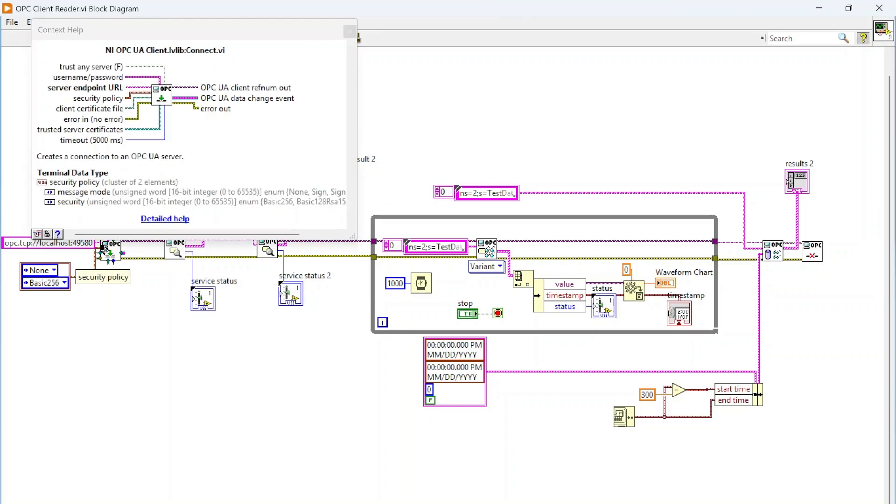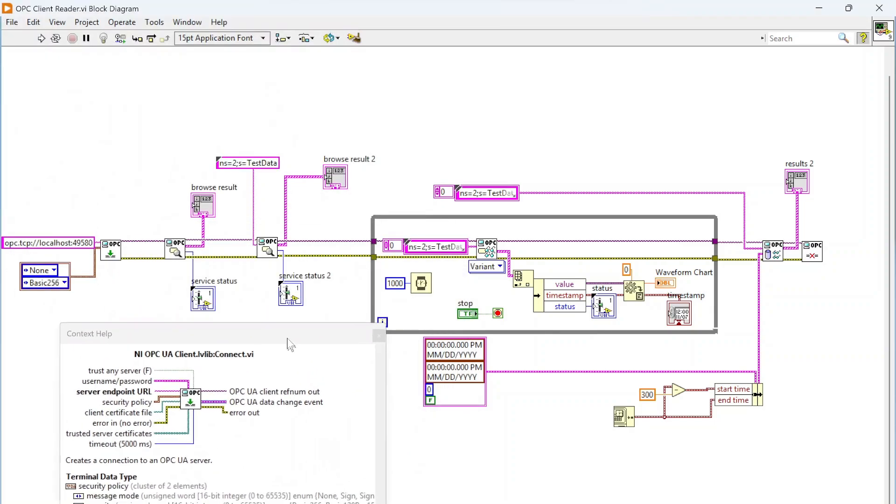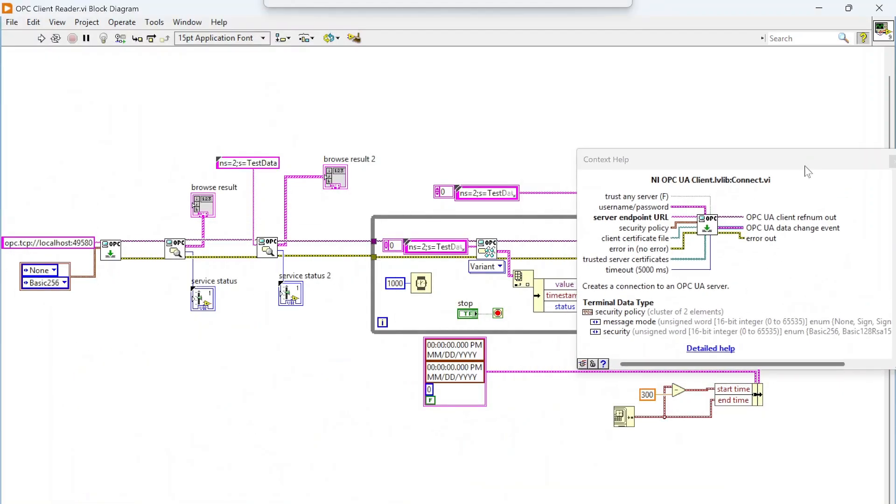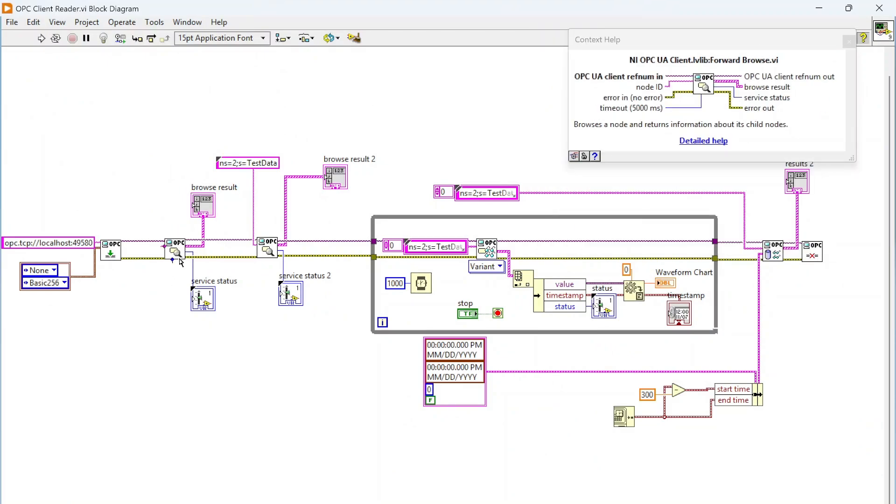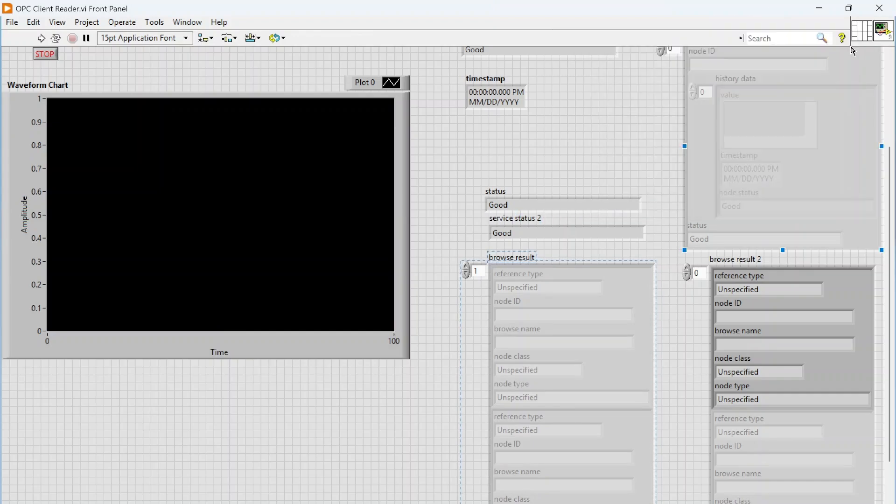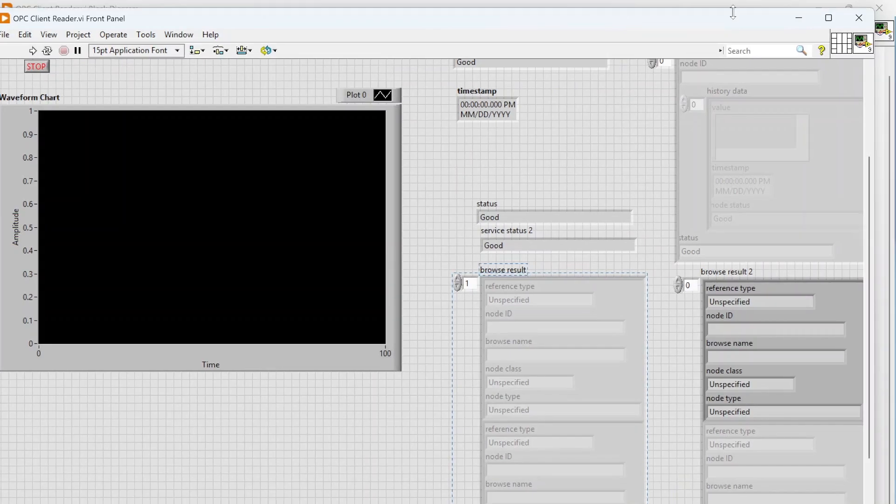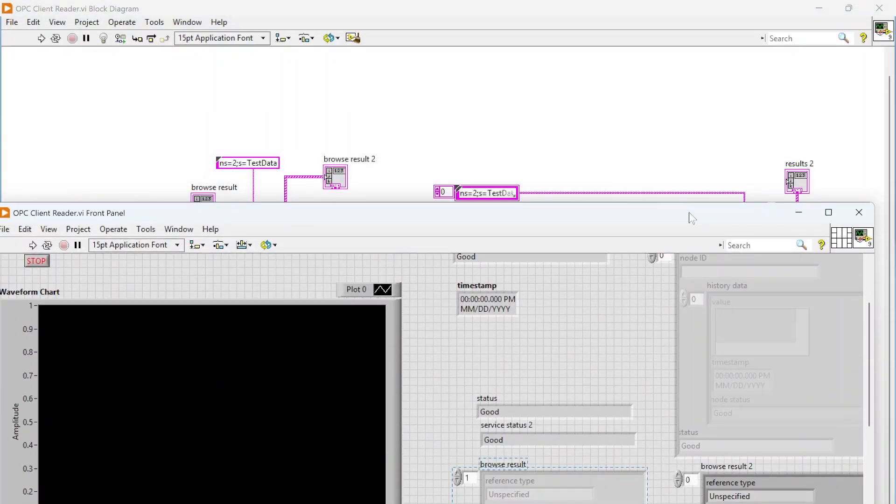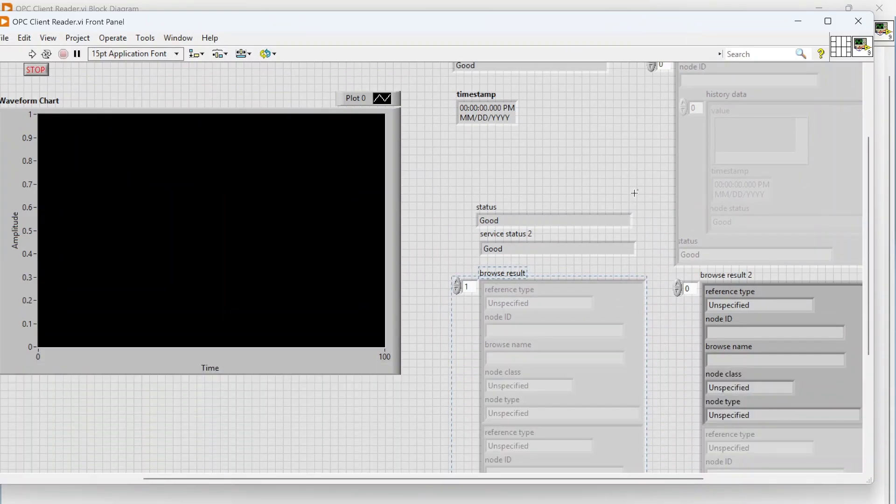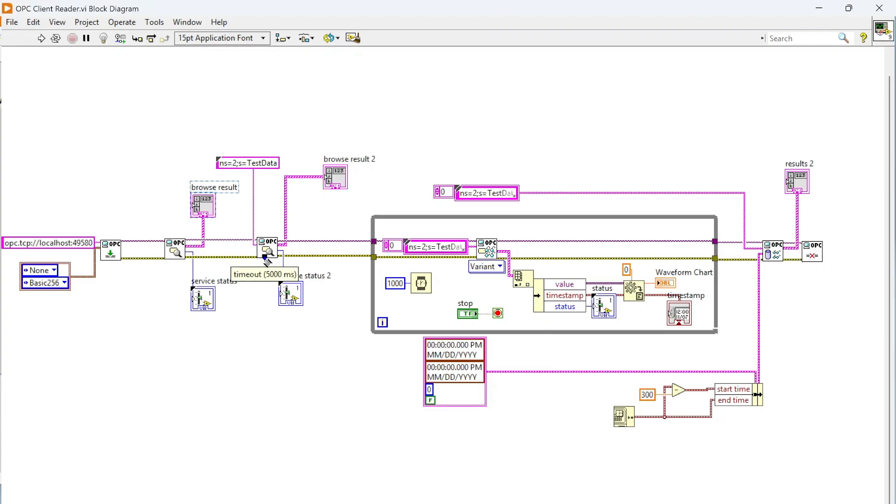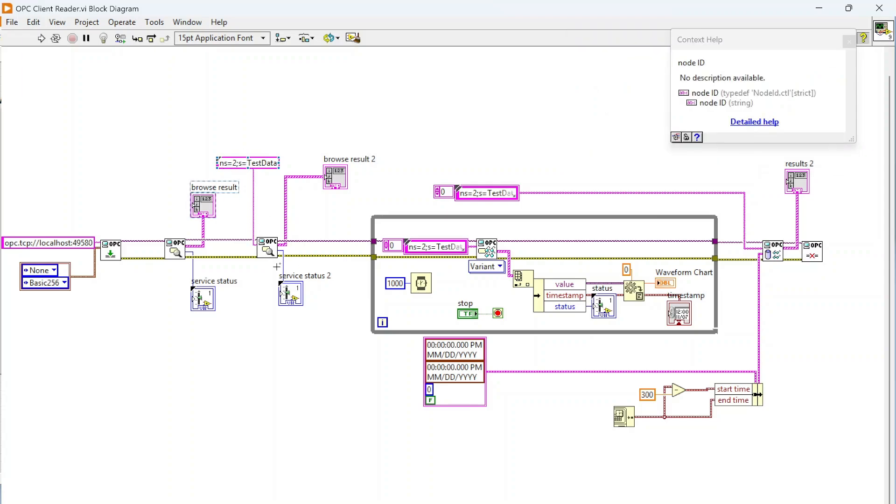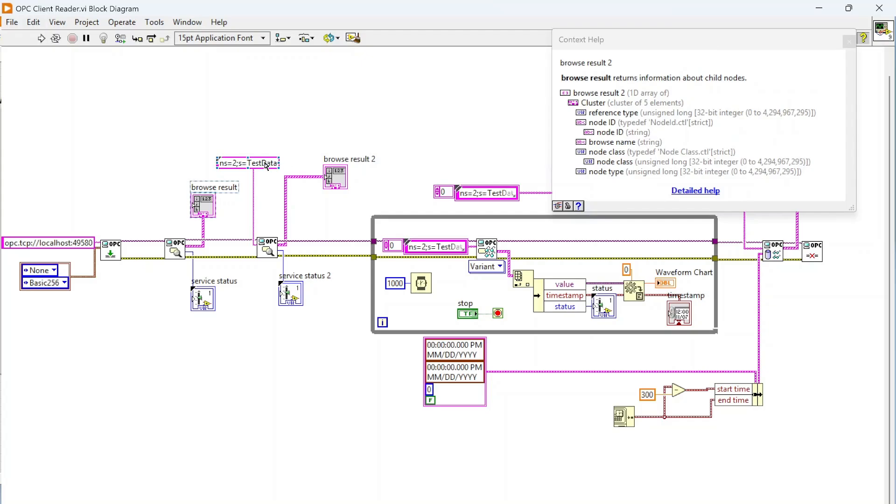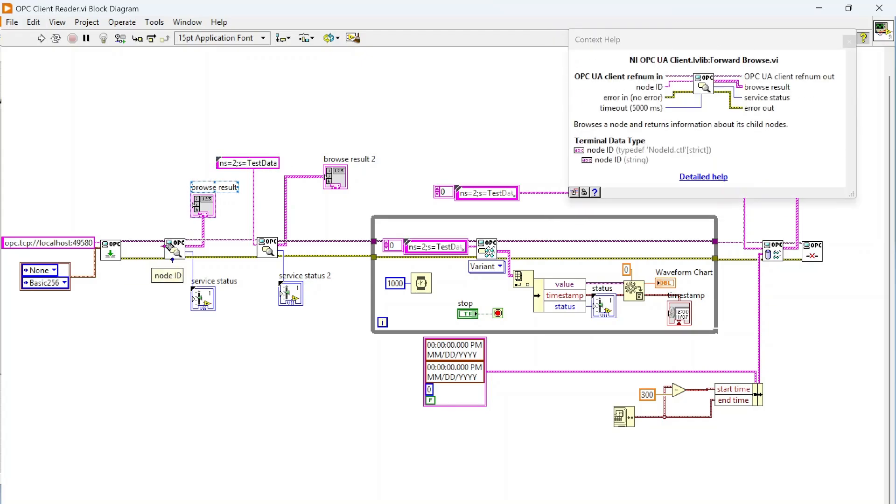We have the same thing, this OPC connect to connect to our server. I'm also using this forward browse which returns this browse result, which is essentially a list of available items and folders for this server. You can query that and find that stuff automatically. Then I'm doing the forward browse again. This first one had nothing connected, now I'm passing in the data I'm interested in—this node ID—and it's going to return the results for that node ID specifically. This is information about the root node and this is about my specific node.